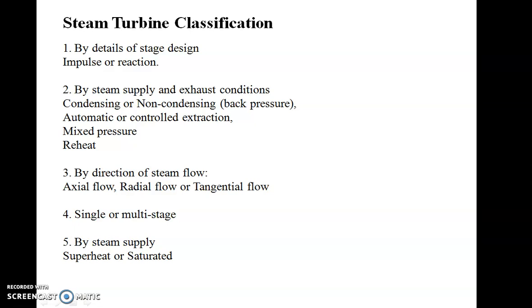Steam turbines are classified basically depending upon different methods, like your hydraulic turbines also we have classified. On the same basis we are going to classify by the details of stage design, whether the action is impulse action or reaction action. Based on that it is classified as impulse or reaction steam turbine. Then by steam supply and exhaust condition, how you are going to supply the steam and what is the exhaust condition of steam. Based on that also you are going to classify the steam turbine, whether it is condensing or non-condensing, automatic or controlled extraction, mixed pressure or reheat type of turbine. Okay, reheating is also one of the important parameters in steam turbines.